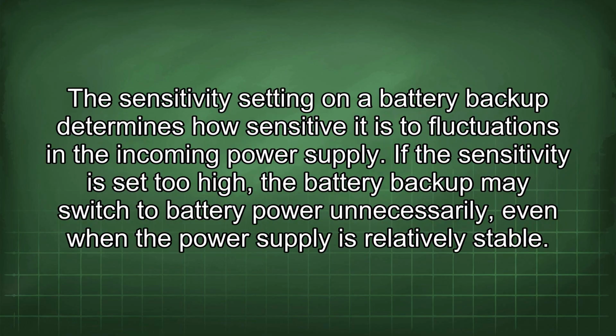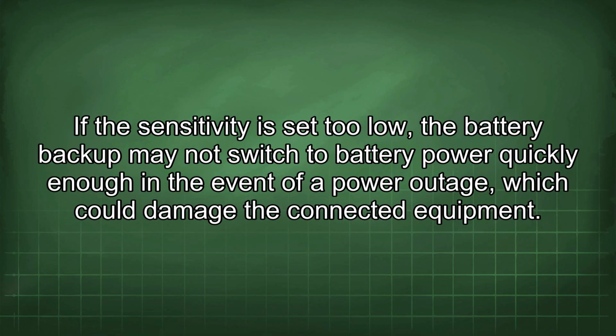The sensitivity setting on a battery backup determines how sensitive it is to fluctuations in the incoming power supply. If the sensitivity is set too high, the battery backup may switch to battery power unnecessarily, even when the power supply is relatively stable. If the sensitivity is set too low, the battery backup may not switch to battery power quickly enough in the event of a power outage, which could damage the connected equipment.